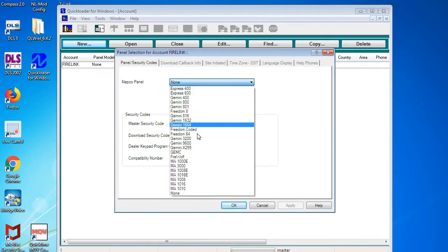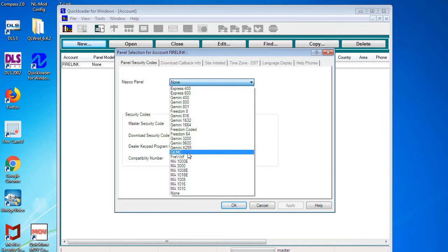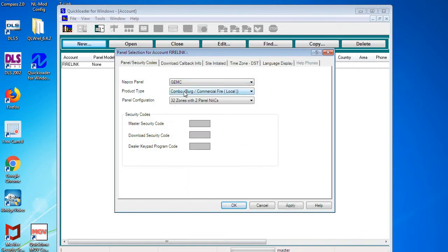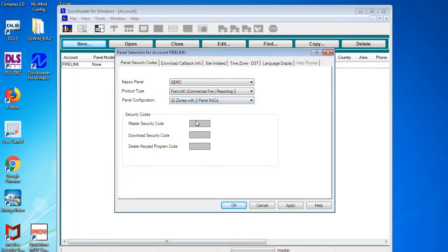Next, we need to pick the NAPCO panel type, so for a Firelink panel you're going to pick a Gem C, make it a Firewolf because it's not a combo, and it's a 32-zone panel with two NACs. Next, you're going to have to type in the master security code, which is located on the sticker in the upper right-hand corner of your panel, and it's always going to be a six-digit number.